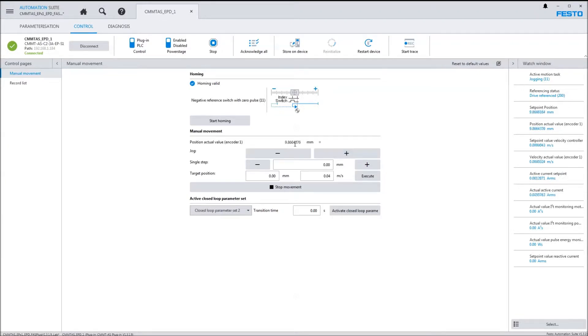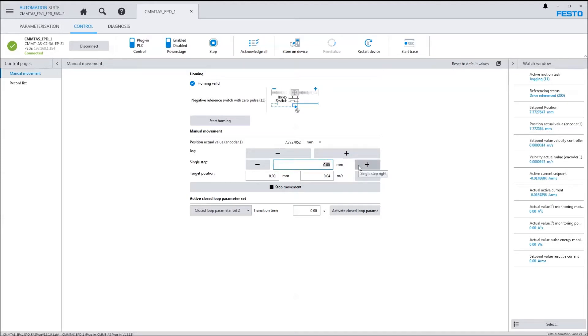I'm going to acknowledge all faults. Back to being green. It's not looking at the negative over-travels anymore and I can jog the axis. Press and hold this button here for plus movements. You see that the position changed. Go backwards or I can go in increments, do relative moves. So millimeters - we're at seven millimeters, do a plus, it should go to 27 millimeters, which looks very good.